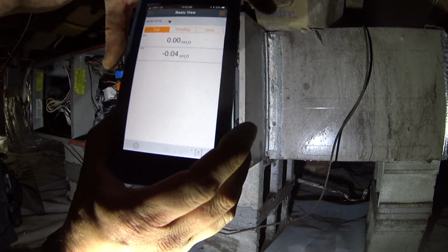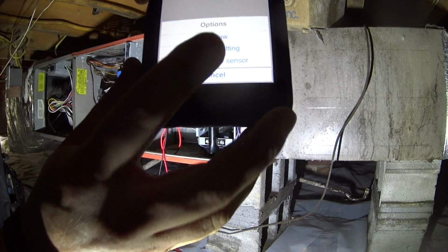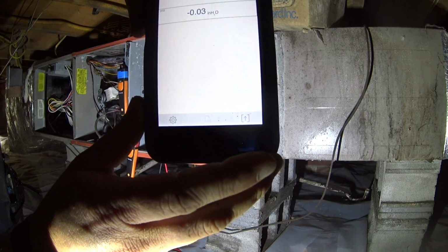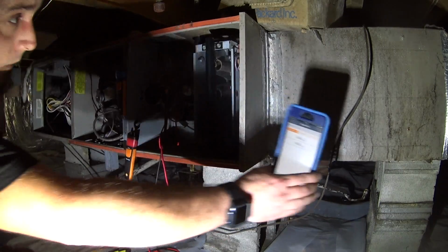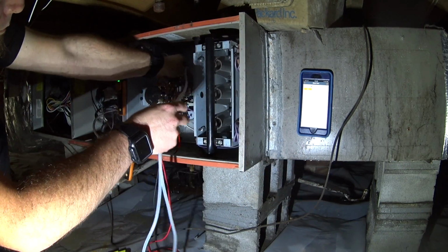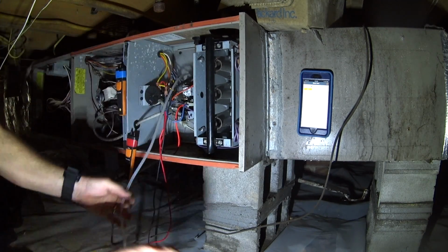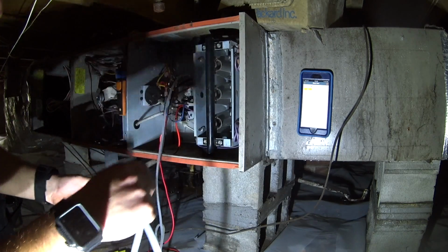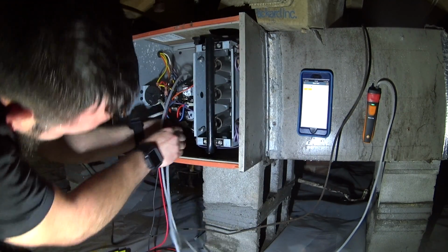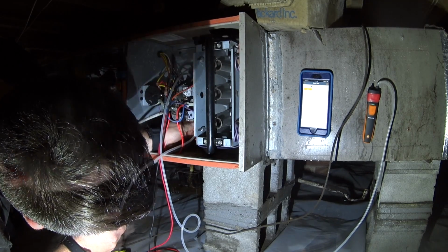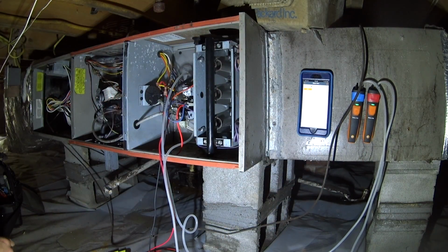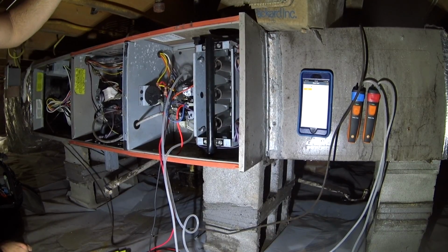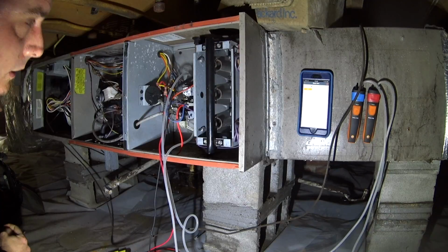Where'd my phone go? The Testos are connected. We're gonna zero them out by hitting the gear at the bottom left, zero pressure sensor, continue, and we are zeroed. Incoming gas pressure goes on the top and goes to the red manometer. Manifold pressure goes to the bottom and goes to the blue manometer. Okay, we can turn gas back on. Standing input pressure is 8.8 inches.